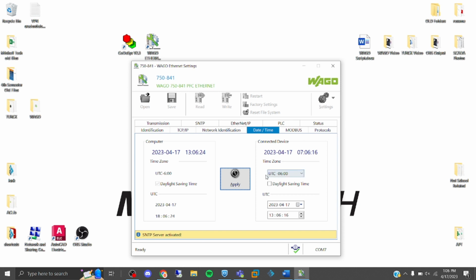If the I/O LED on the front of your Wago PLC is flashing, that's an error code. You can learn the specific error code in the documentation for the PLC. For me, it was a problem with the Wago's clock - simply applying my computer's system time to the Wago PLC fixed that issue.